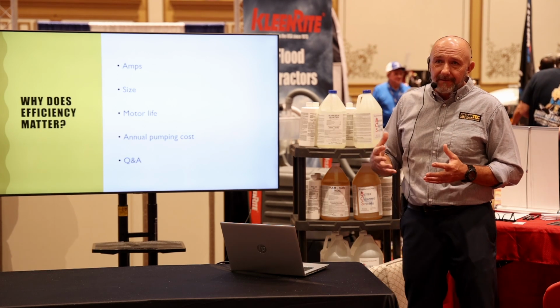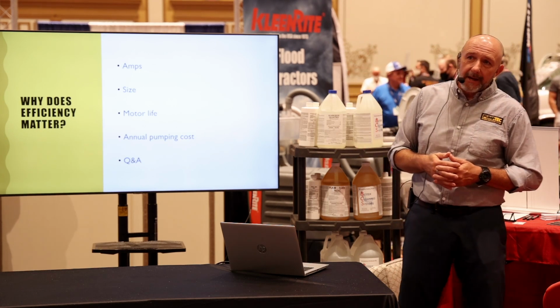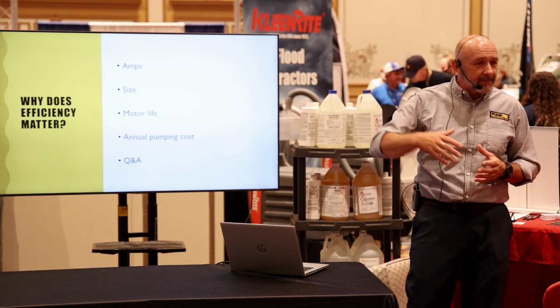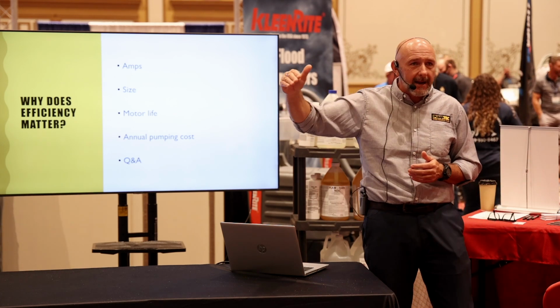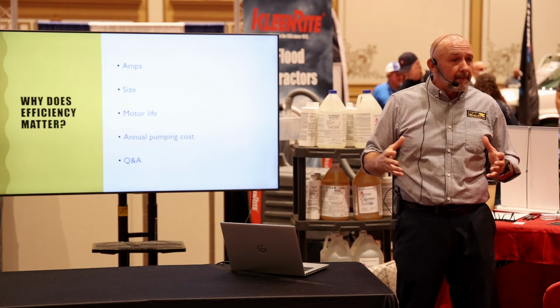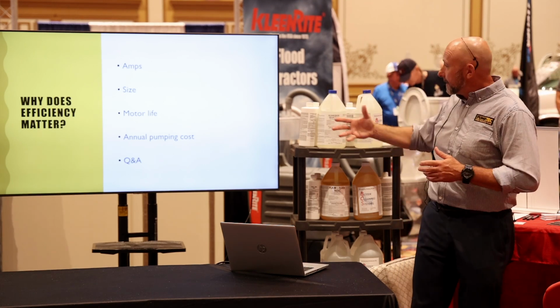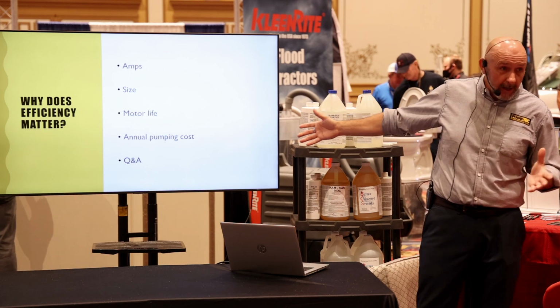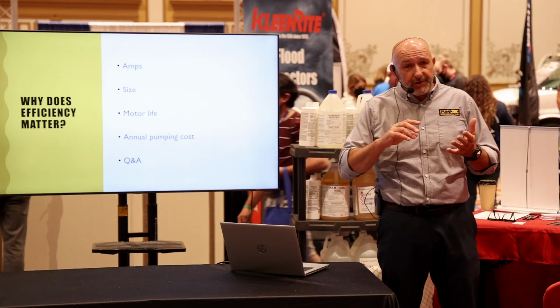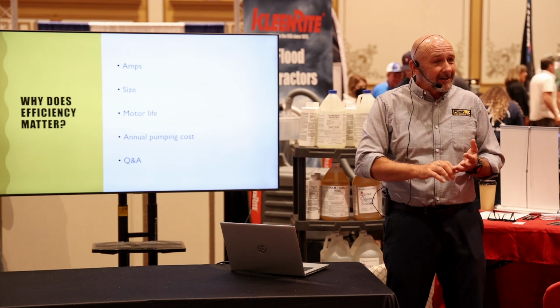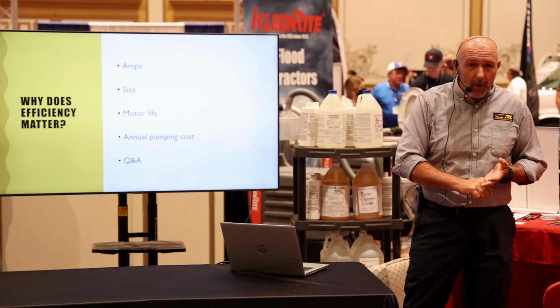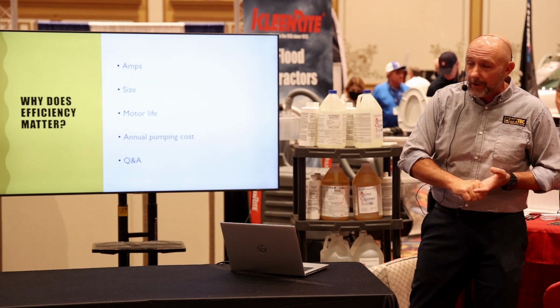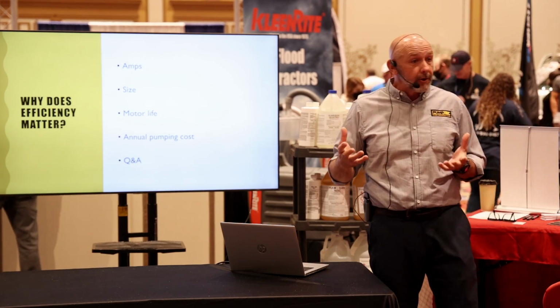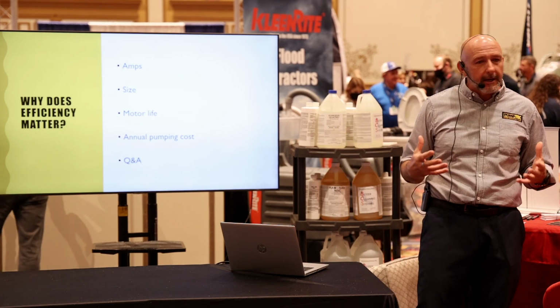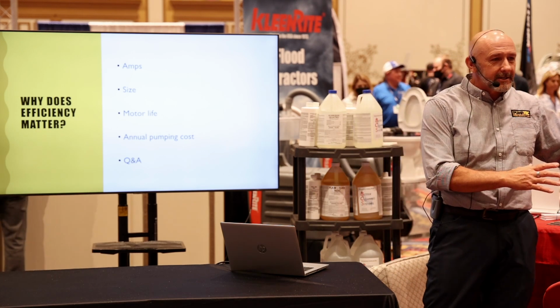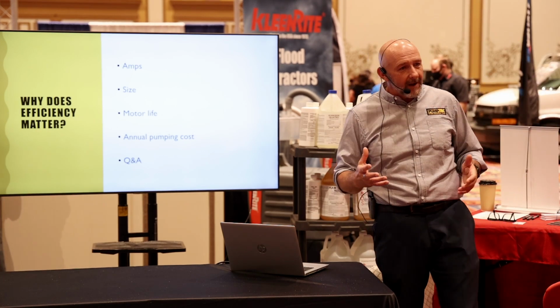And then motor life. Motor life can truly be affected by inefficiencies. Using the example of the higher amps at the same performance, what's happening at that higher amps is it's actually wearing that motor out prematurely. And that comes at an annual pumping cost loss. So it's going to cost you in downtime. It's going to cost you in the labor to install the new motor. It's going to cost you in the actual cost of the motor. And it's going to cost you in actual energy usage, which is not something we typically care a lot about because we're usually playing on somebody else's energy bill, but it's still an important factor to consider.